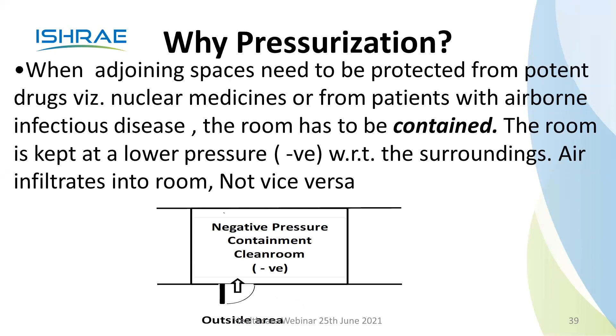The pressure differentials recommended for isolation rooms are as follows. Protective isolation room, that is your positive isolation room, it has to be 2.5 pascals, ideally more than 8 pascals. That's the recommendation from CDC. Airborne infectious isolation rooms, for example for COVID patients, are kept under minus 2.5 pascals.